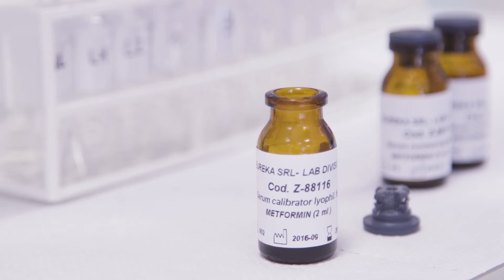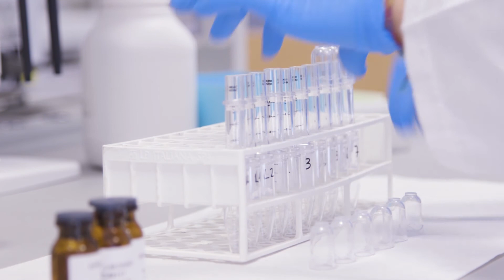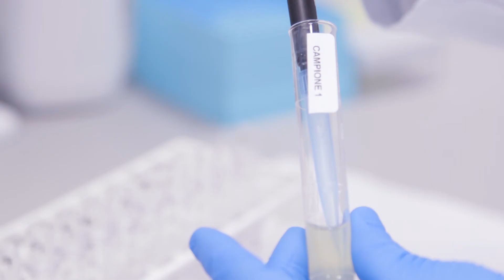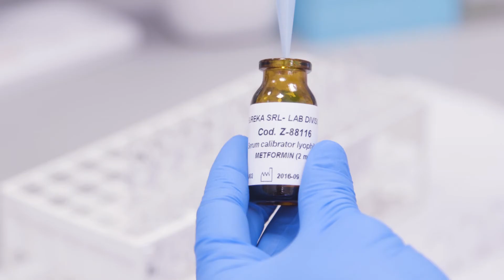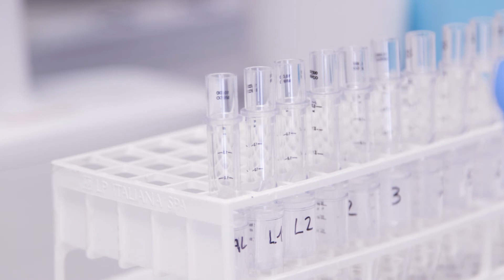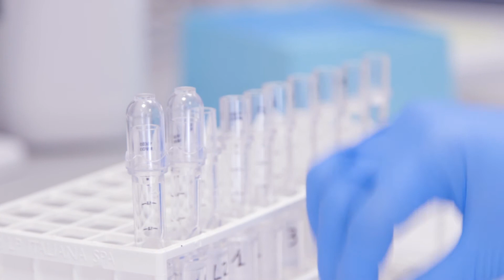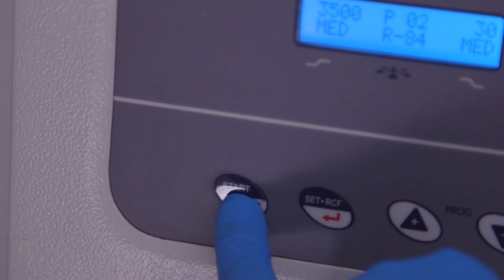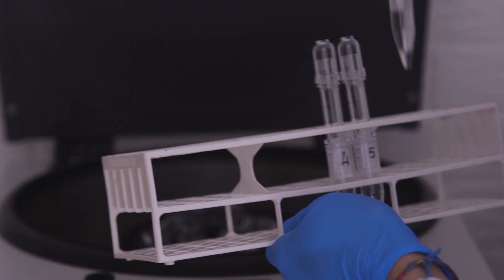Let's go to the workbench and reconstitute the calibrator and the lyophilized controls. Let's take the filters included in the kit and let's go for the analytical session. I suggest you name them on the bottom or on the filter collecting cone. Remove the cap from each filter and add 300 microliters of sample, lyophilized control or lyophilized calibrator. We close the filters with the cap. Now centrifuge all filters at 3500 RPM for 30 minutes.